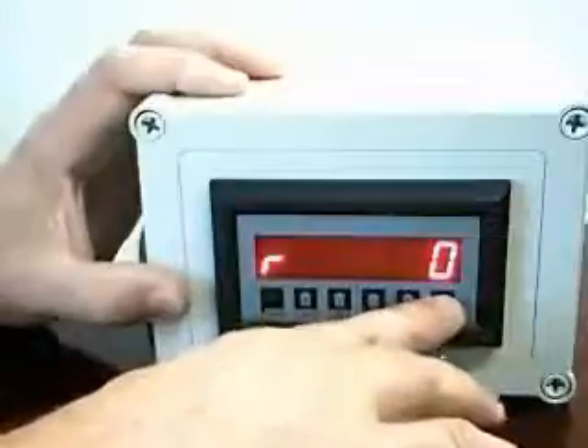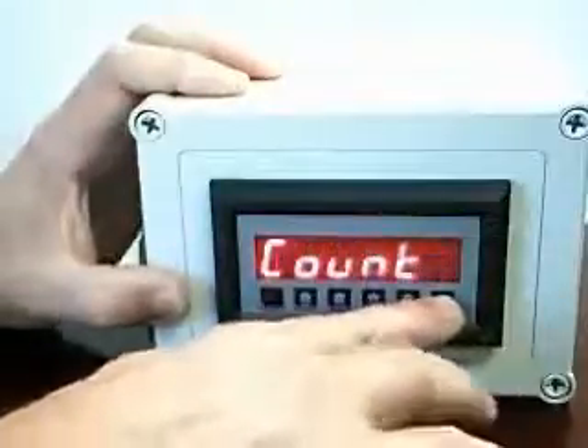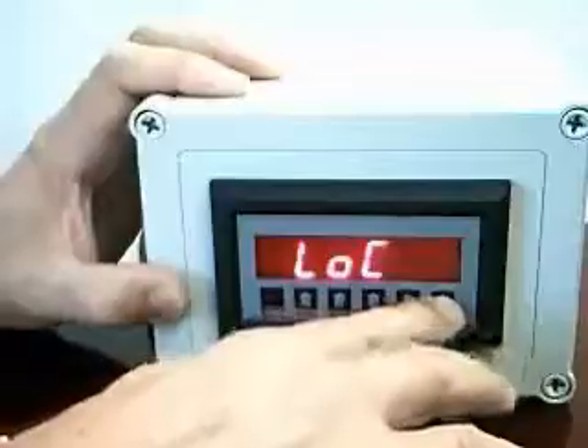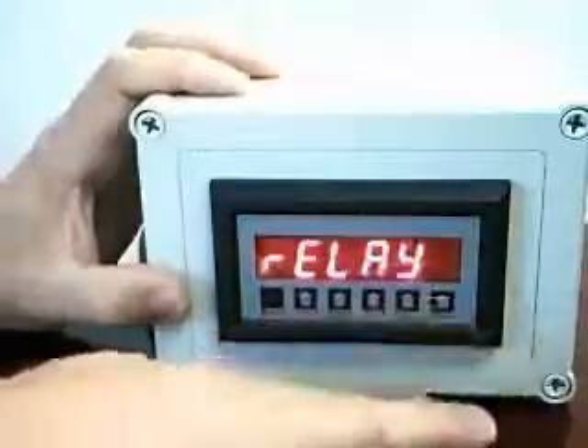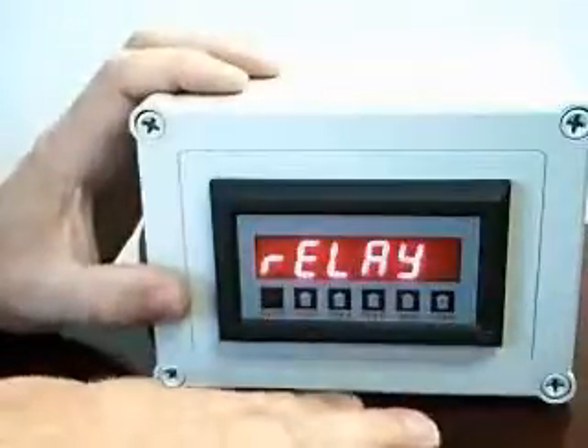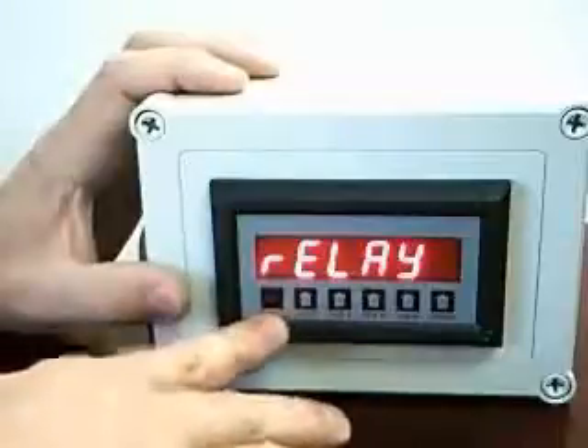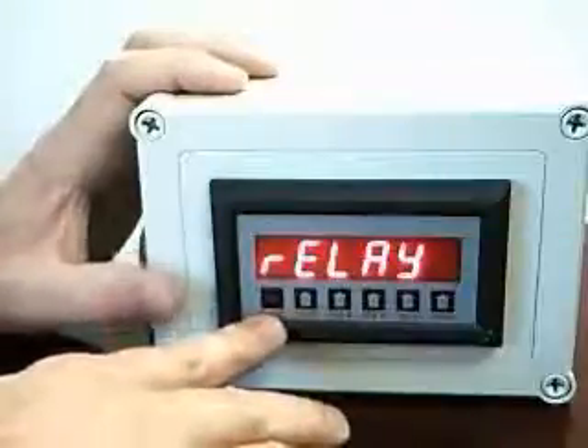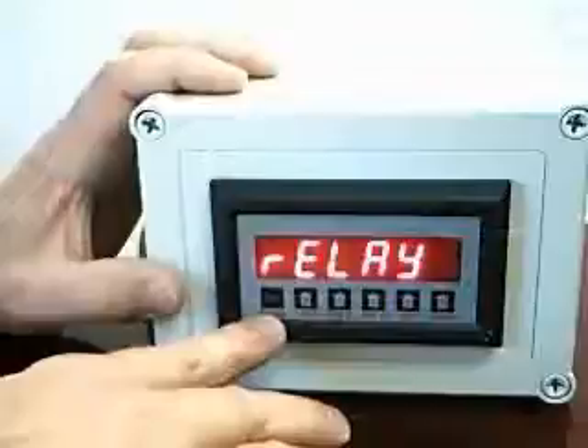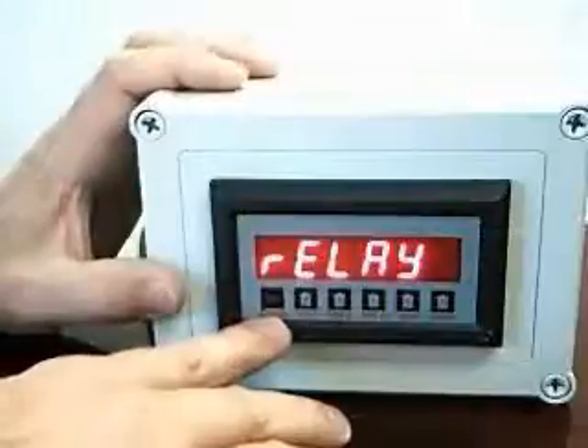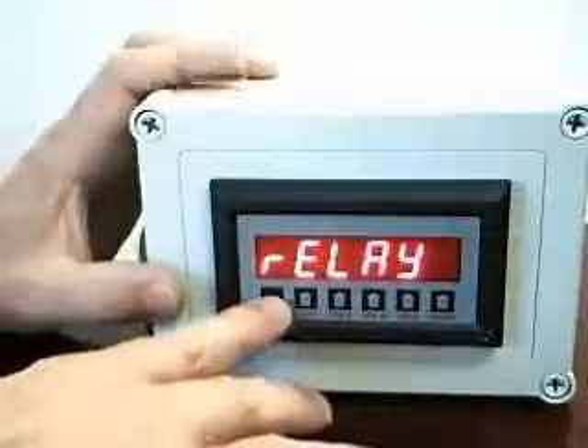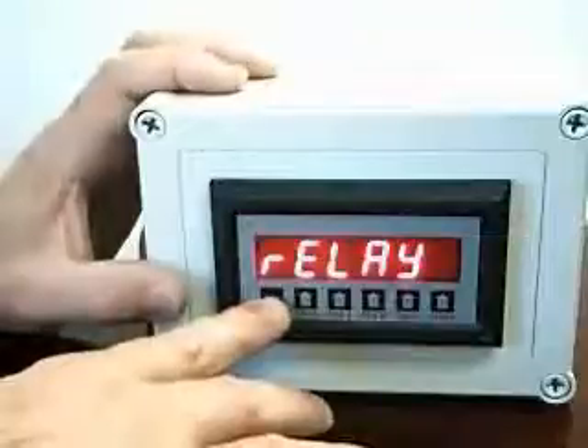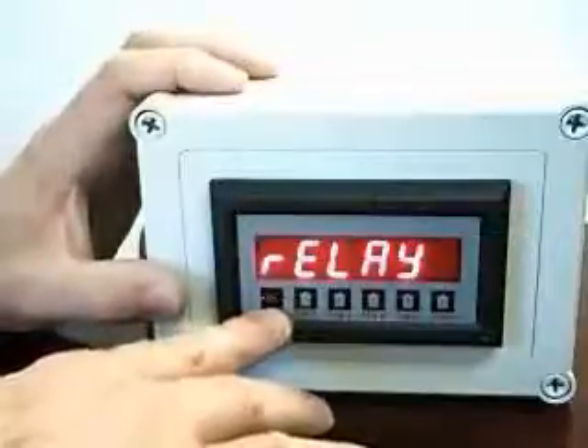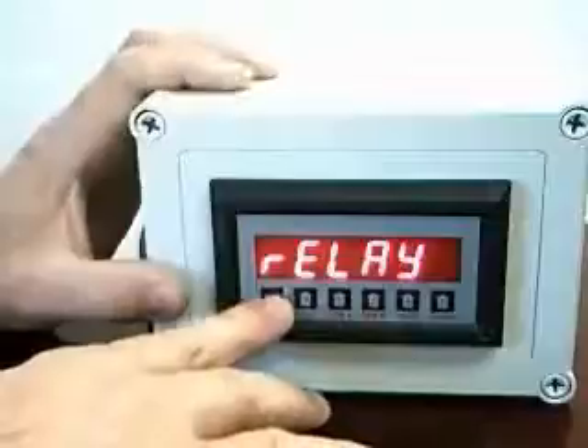There's one further menu in this instrument, and this is associated with the relays. In our application, I'm going to set the relays to function as high and low flow rate alarms. There are 2 relays, so we'll be asked questions on 2 separate relays. So let's go into that submenu group by pressing enter.